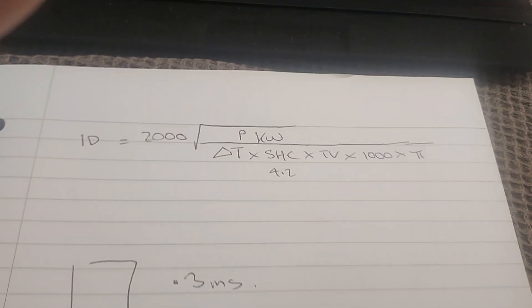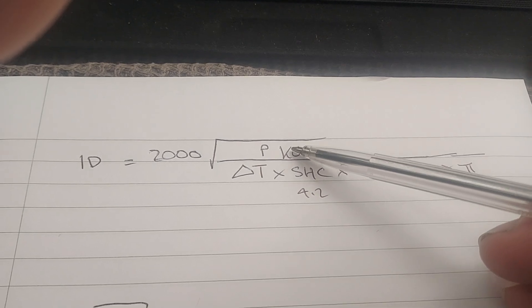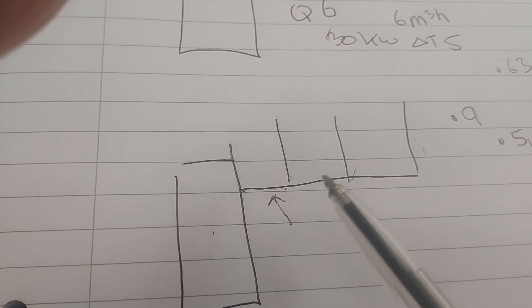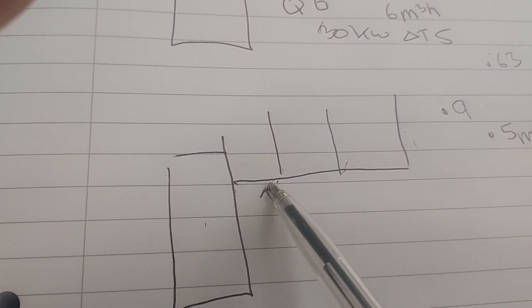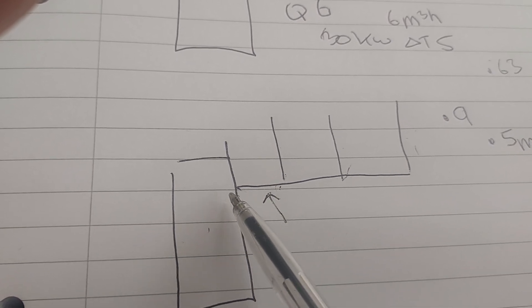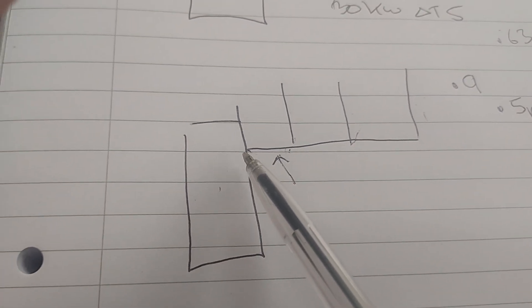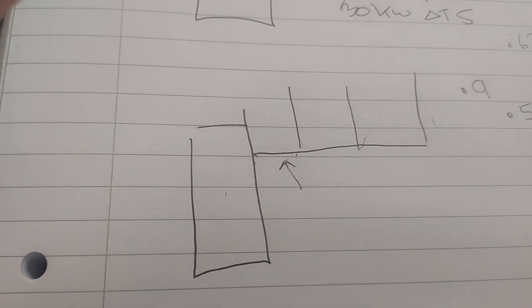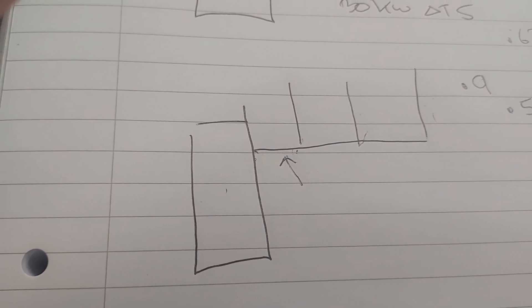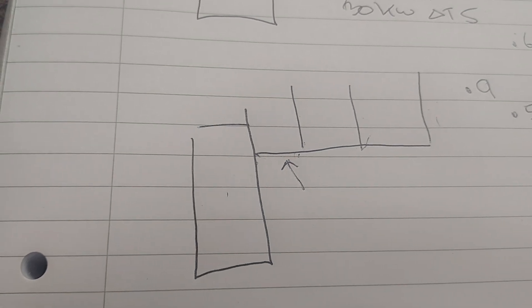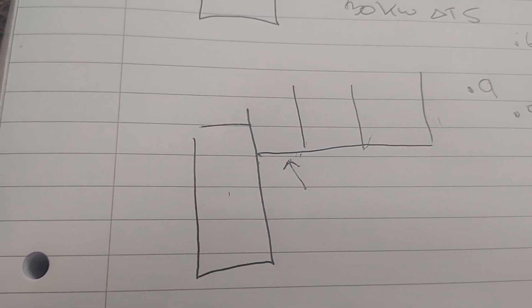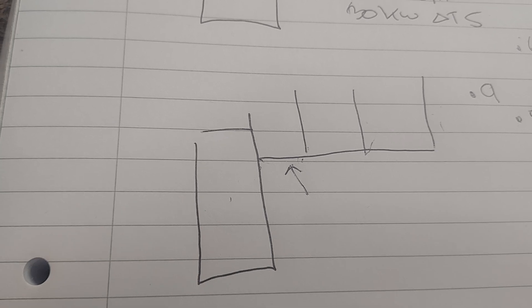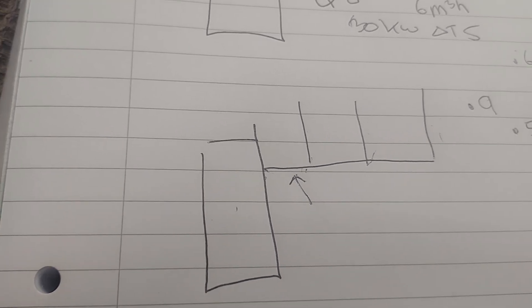We would be putting this one in the formula: 9 kilowatts, target velocity of 0.5, and that would give us the required pipe size for this pipe. Now I've done a few now where I've needed 35mm on this first section of a distribution header, and the tappings on the Q6 from Viessmann are inch. So I did find that you can buy some inch to 35mm male irons, but they're very difficult to get hold of and it looks a bit strange if you don't use those fittings out the header.